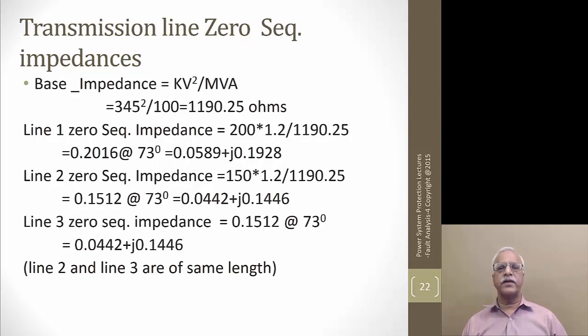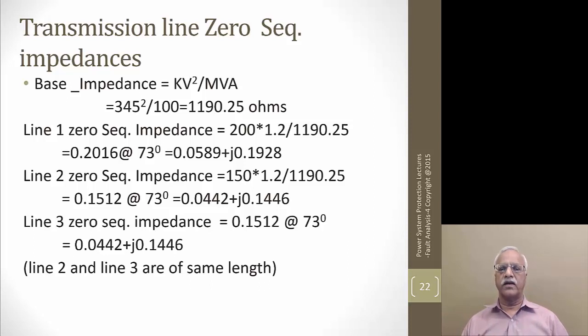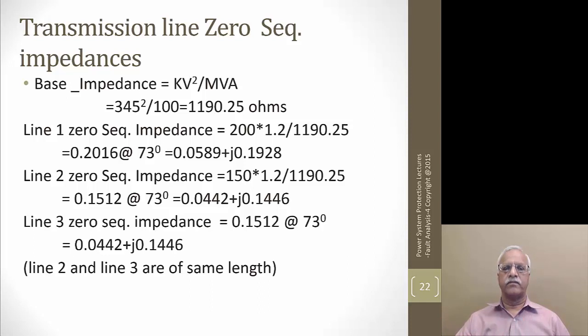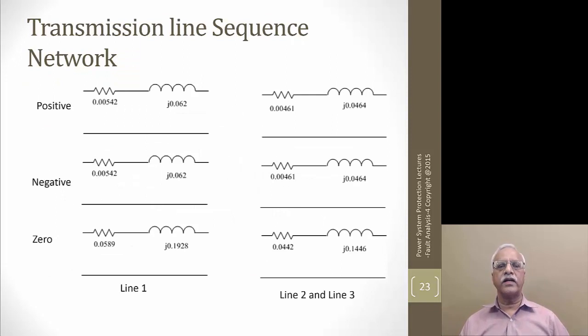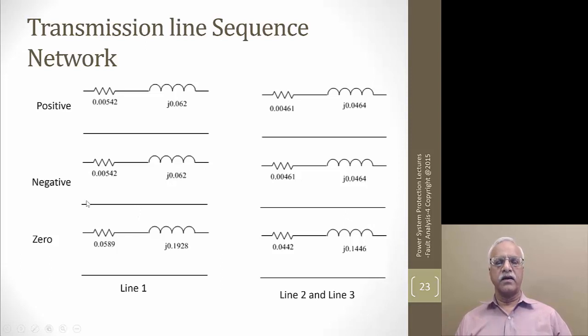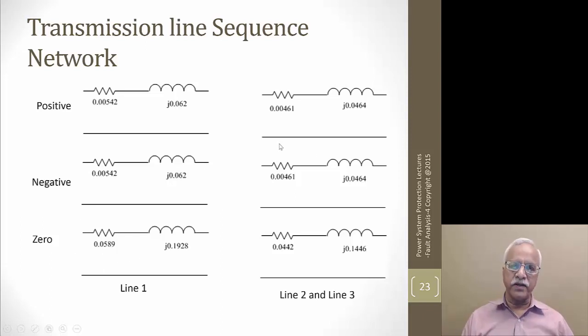For transmission line zero sequence impedance, using the same base impedance of 1190 ohms, line 1 zero sequence is 0.0589 + j0.1928 per unit. Line 2 and line 3 have the same line lengths, so their zero sequence impedances are 0.0442 + j0.1446 per unit each. The whole network showing line 1 positive sequence, line 2 positive sequence, negative sequence, and zero sequence networks are shown here, with line 2 and 3 having identical impedances.